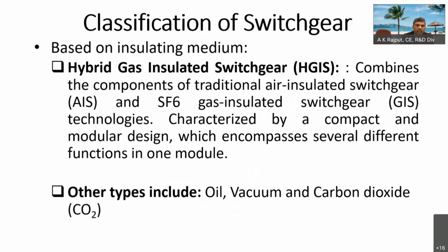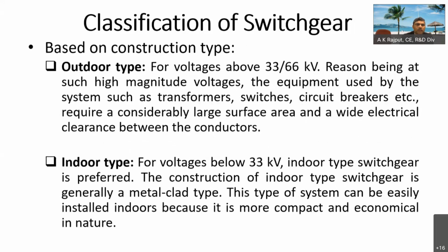Then hybrid gas insulated switchgear, which the presenter just before me presented very nicely. The hybrid switchgears are also there, with solid insulation bus bar and all those things, so let me not repeat it. Other types of classification include oil, vacuum, carbon dioxide based, or air-filled, compressed air-based switchgears. Based on the construction, whether we are installing outdoor installations, the terms are self-explanatory, so I am not going to read all those things.